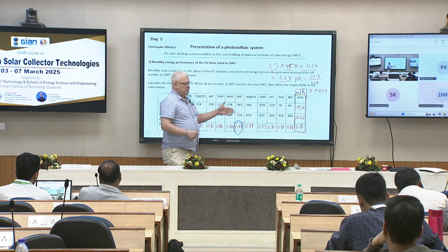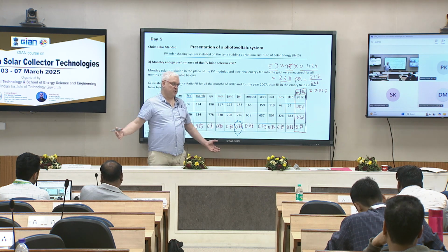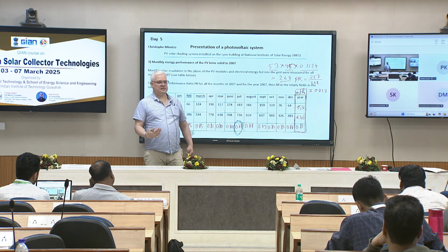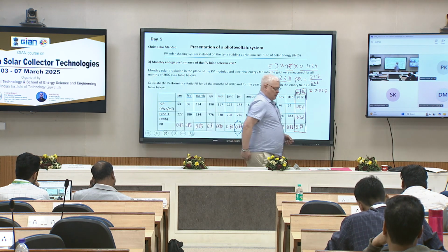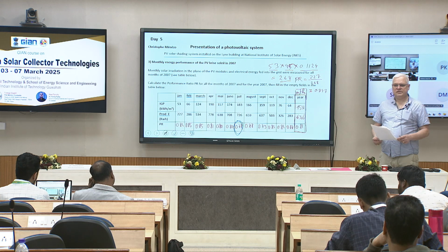A PV central will produce more on sunny days because the days are longer and there is more sun, but the performance is less globally because of temperature, which could also be linked to soiling or things like this. So this performance ratio is very interesting to see if the PV central is operating in good condition.